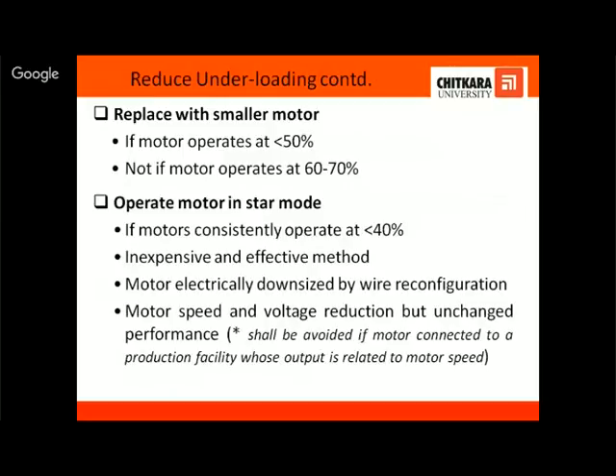Now, if the motor is underloaded, what kind of recommendation can you give? Replace it with a smaller motor if the motor operates at less than 50% of the load, but don't replace the motor if it is operating in the range of 60 to 70% load, because then you won't be able to recover your cost. And if the motor is consistently operating at a load of less than 40%, then for delta motors, most of the time they are delta connected motors.